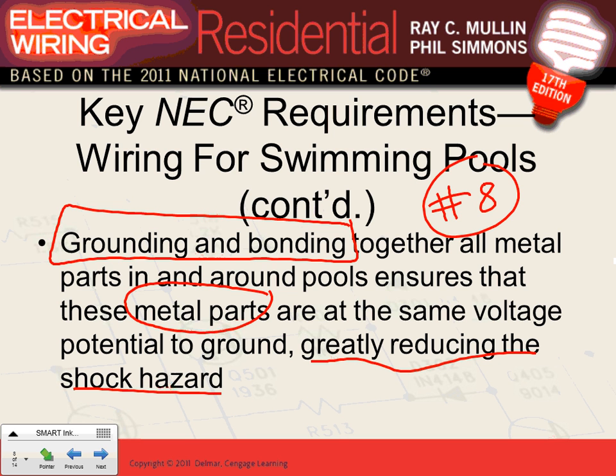So why do we have number 8 conductor bonding everything together, guys? To put them all at the same level. So if there's a short circuit or a fault, it trips so fast before it goes through your heart.